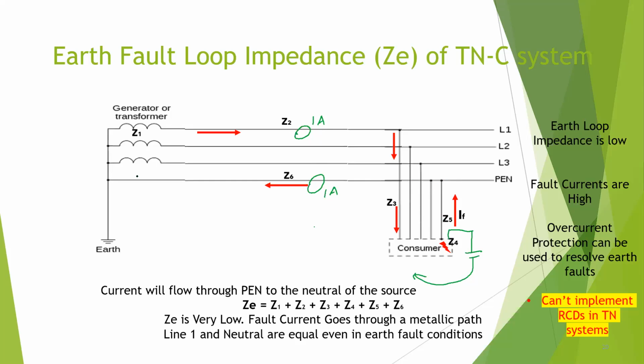So it is one of the disadvantages of the TNC system, and this is the least safe system in the earthing system category. The other thing is, in the TN system, earth loop impedance is low. All the paths are metallic. Your current is coming here, going through the enclosure and again going to the neutral, flowing through the neutral to the neutral of the source, and therefore the whole earth loop is made out of metallic wires. So loop impedance is low, and your fault currents will be very high in the TNC system. Therefore overcurrent protection devices can be used to resolve earth faults, but it is not very effective. We will see why.